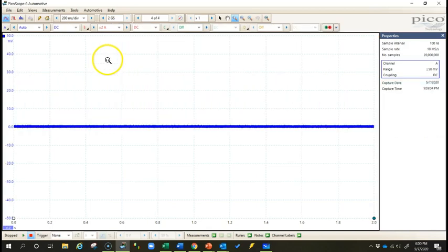So first, and probably one of the most obvious things that we can do to increase our sample rate, is to change the time base. As you can see right now, the way I've got this scope set up, I've requested 2 gigasamples. It's actually giving me 20 million samples, and dividing that across 2 seconds is 10 million samples per second.